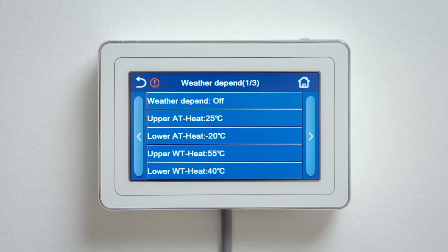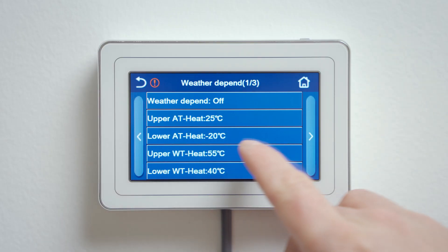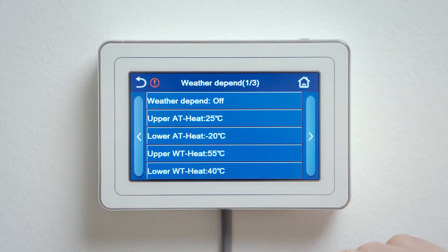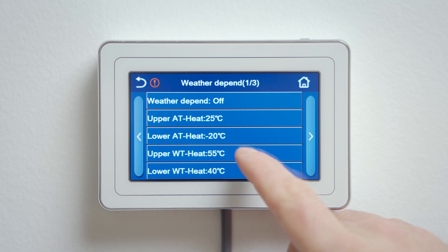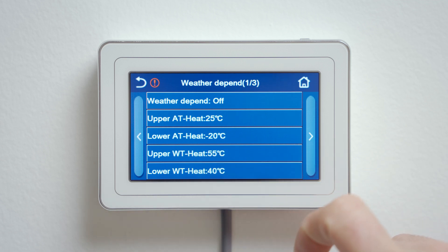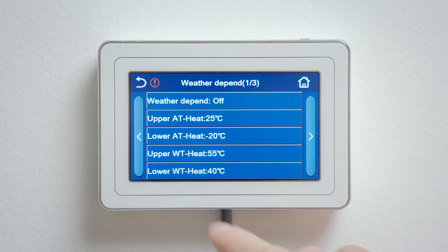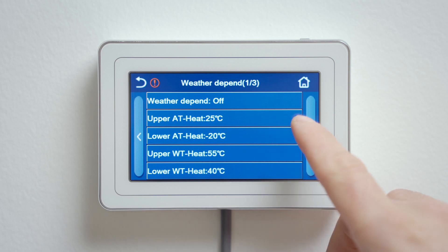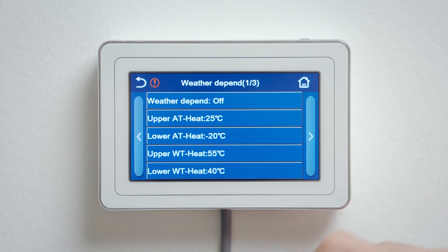From the second to the fifth line you will find temperatures that say the following: when the outside temperature is minus 20 degrees, the heat pump heats the heating water to 55 degrees Celsius. When it's 25 degrees outside, the unit heats the water to 40 degrees Celsius. This is the factory setting and will surely need to be changed.